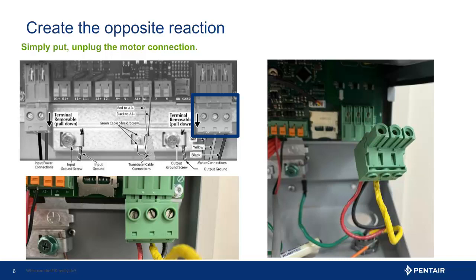You may wish to turn off the drive and reconnect the motor. Turn the drive back on and reset and start the drive. Does the high amp fault return? Then it is most likely the motor. A good place to start troubleshooting is proofing the wires, ensuring they are secured tightly into the harness. This is often the case, and simply proofing and tightening the connection can resolve the issue.